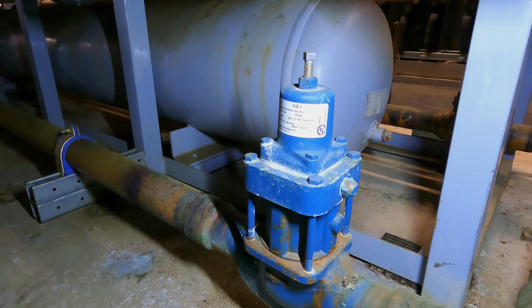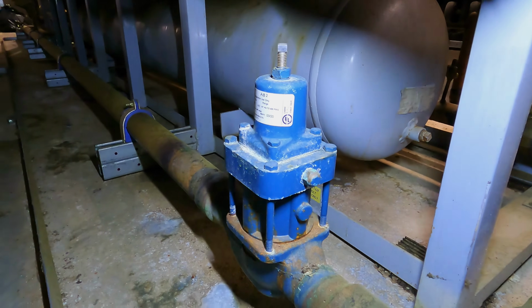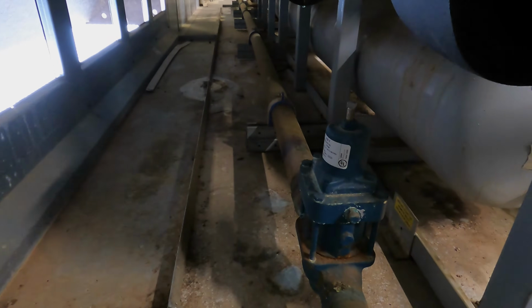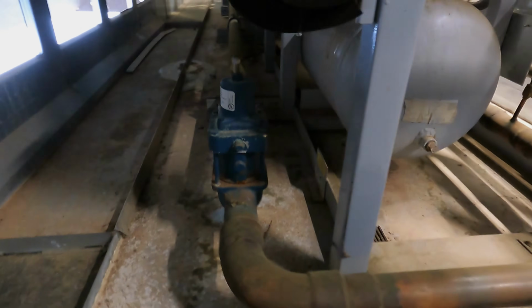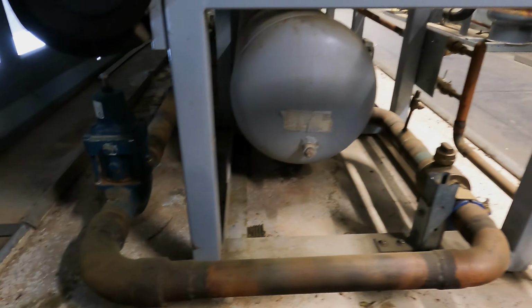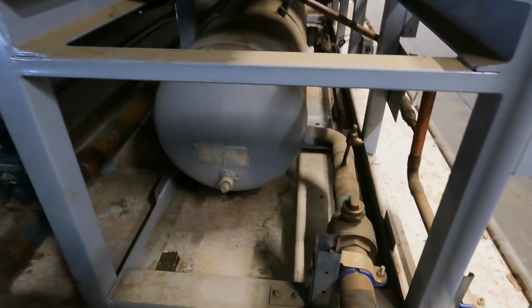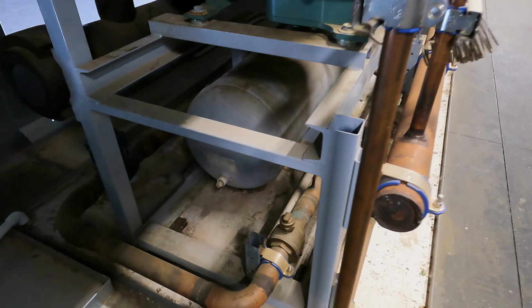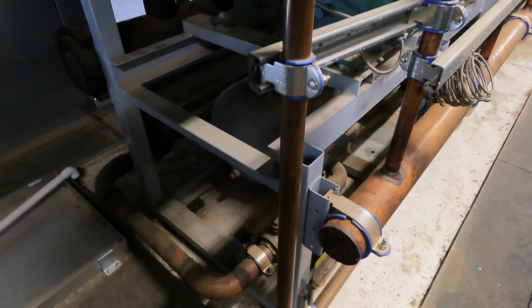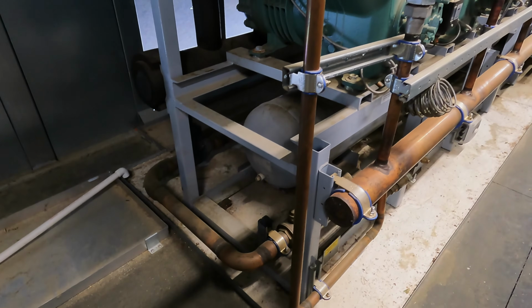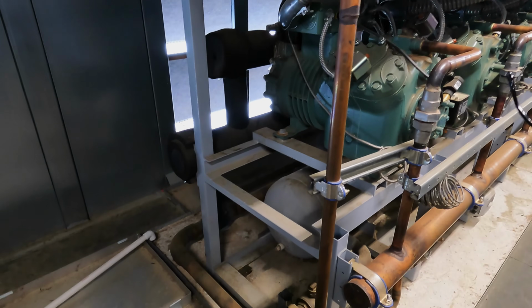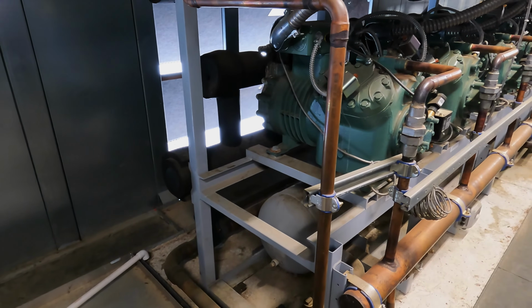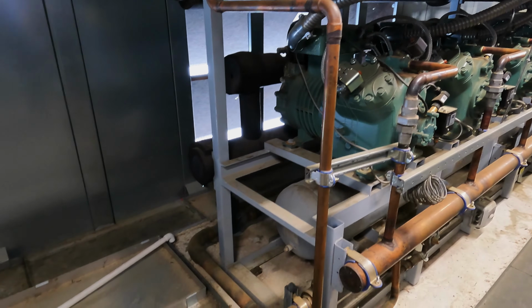You see the blue valve back there? That's a holdback valve. That's what we call it, the A8 valve. All it's going to do during low ambient conditions is hold pressure back on the condenser because we want to keep our head pressure up. If we get too low of a head pressure, none of the system will work. So during low ambient conditions, that thing doesn't energize, but it's got a pressure regulator in there that forces it closed off a little bit.